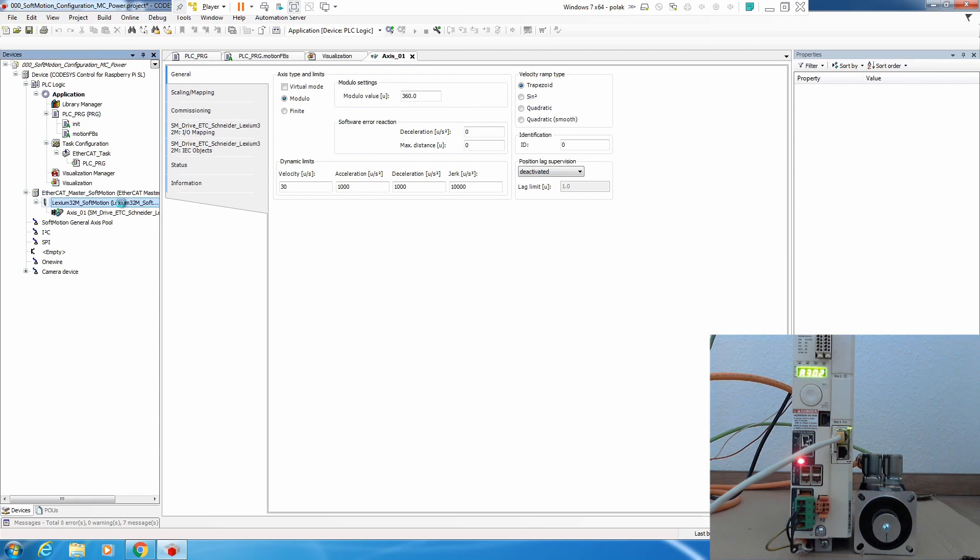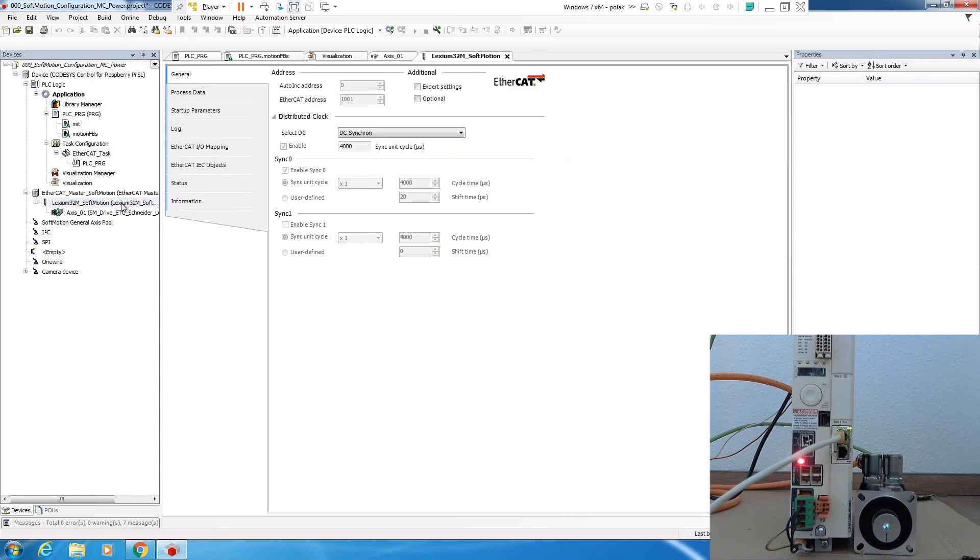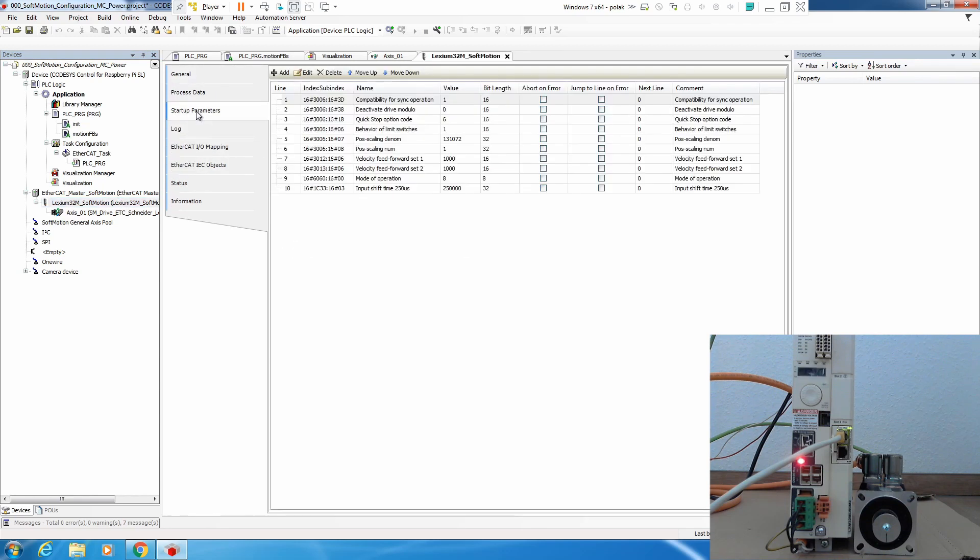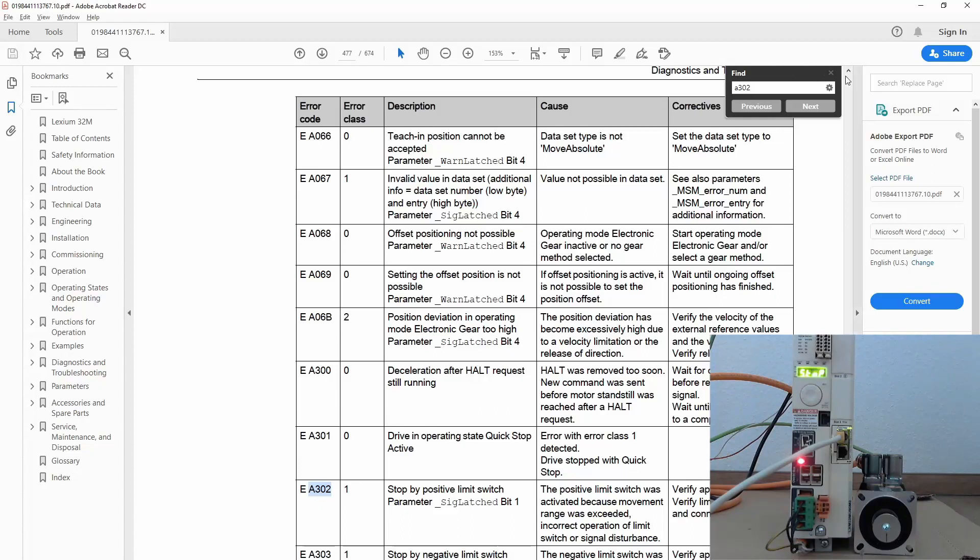Now by default the limit switches inside the drives are active, we need to disable it. The easiest way is to disable it using startup list inside our drive on EtherCAT. We click on our drive and there is a startup parameter list. How to disable limit switches is described in the product manual and on page 384.